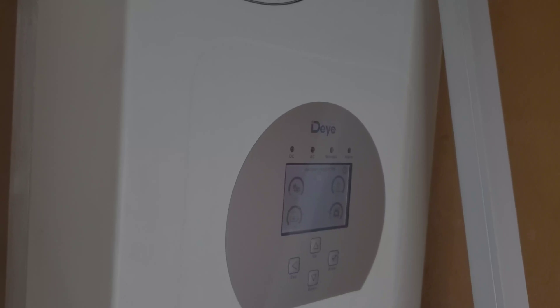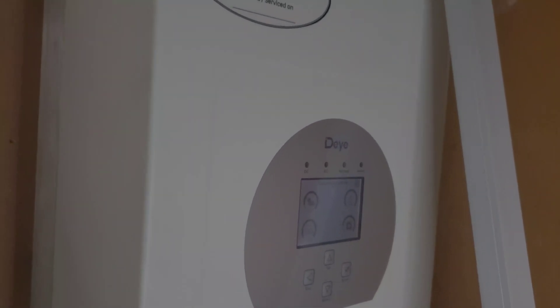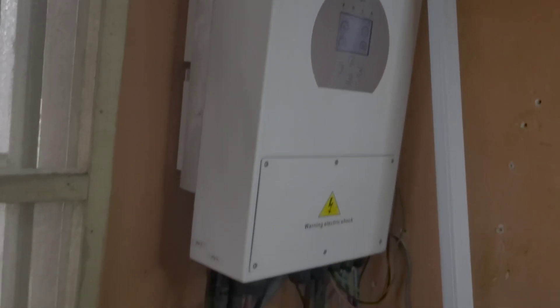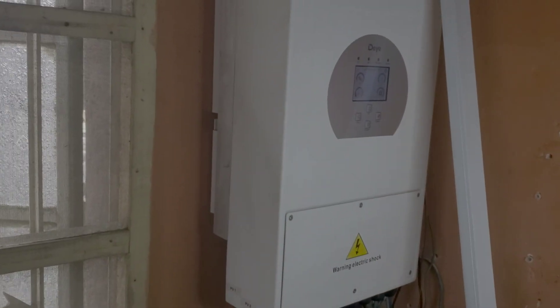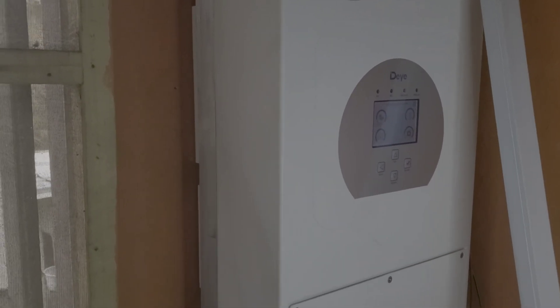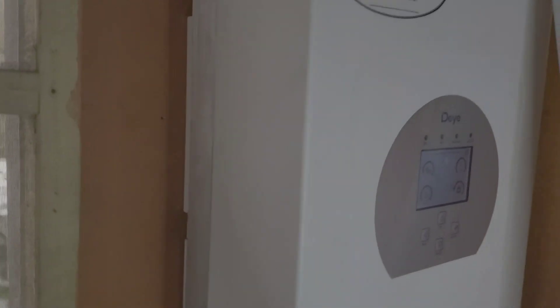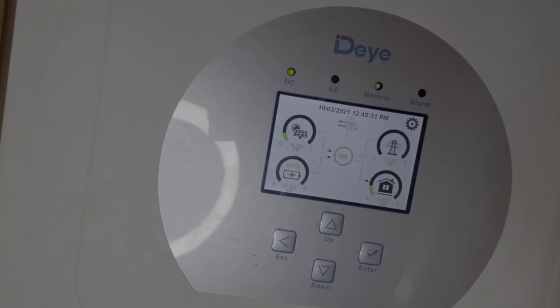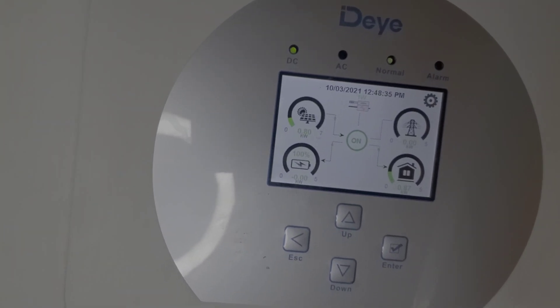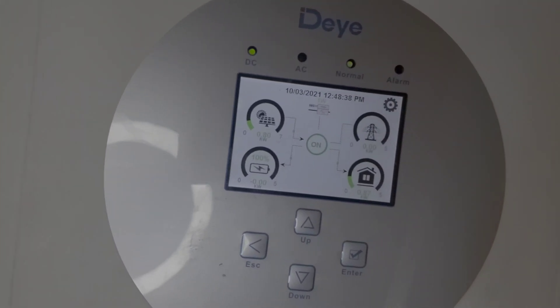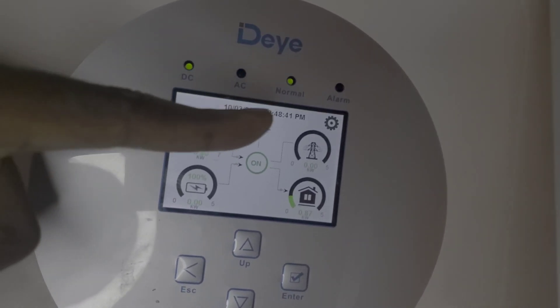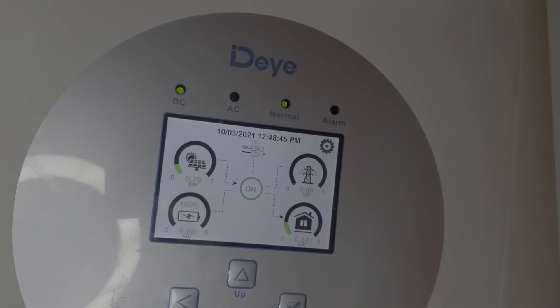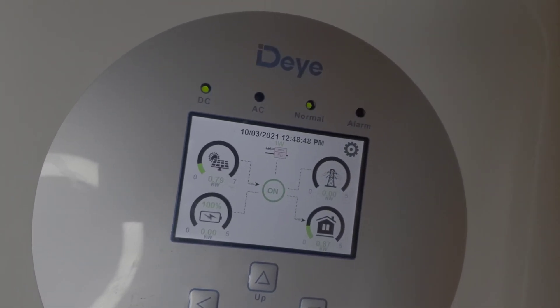Where it's feeding from that inverter directly into this inverter. So this inverter forms the grid. Now this inverter also continues to communicate with that inverter based on what is happening. So as my battery goes through different stages of charge, I can do up to 100 amps, that's what my BMS allows. So as it goes through different states of charge, I'm pushing 100 amps in, and then what happens is the BMS starts telling the inverter to limit what can be sent to the batteries.